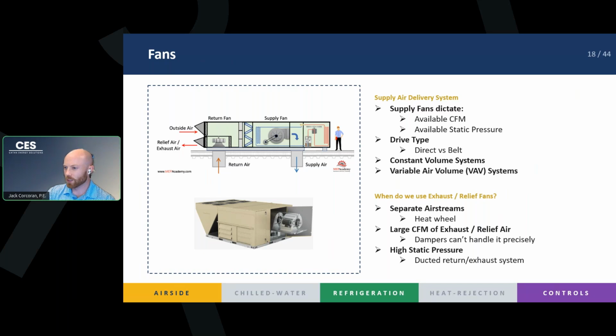Another situation where you would use an exhaust or relief fan is if you have large volumes of exhaust or relief air and the dampers can't handle it as precisely. You can imagine that just opening and closing dampers is not going to dial in your CFM very precisely. So if you have a huge volume, you have big dampers, and it's much easier to dial in a CFM at fans than with dampers. So if you have large CFMs, that's another reason you can use them. And lastly, another reason would be static pressure. If you have a fully ducted return, that static pressure can quickly add up, and maybe the supply fan can't handle it. So you could have low CFM, high static pressure. You don't want a massive fan for 800 or 1,000 CFM. You maybe just separate it out into two fans and call it a day.